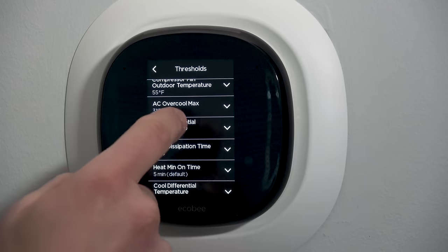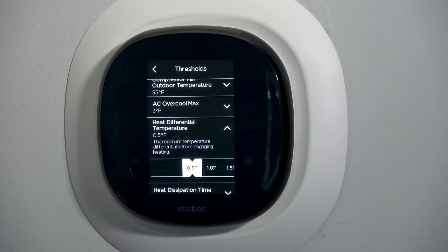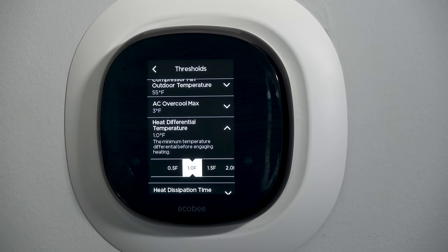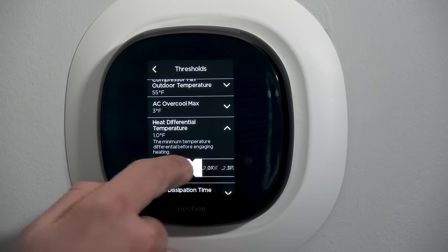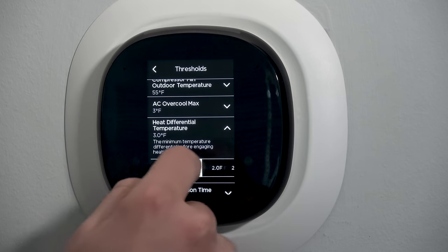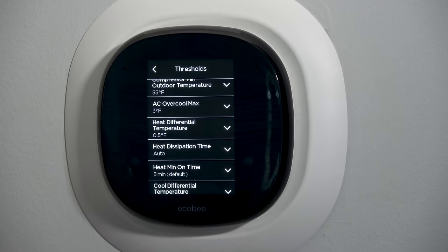Heat differential temperature: 0.5 degrees means it's going to wait a half degree before it turns the heat on. If heating is set for 70 degrees, it'll wait till 69.5 to turn on and run until it's back up to 70, then shut off. Half a degree is pretty good — you could make it a full degree. I would not make it more than that; if you set it to 3 degrees, someone asking for 70 degrees having to wait till it drops to 67 is not going to be happy.